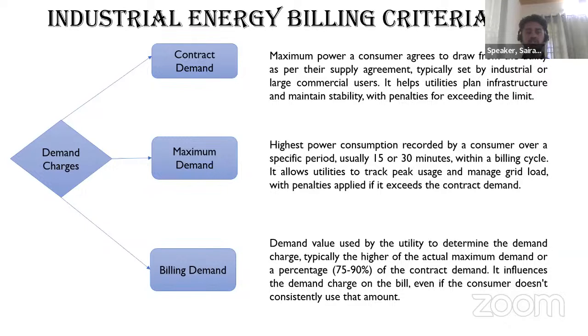Then coming to the demand charge, there are three main terms in the demand charges: contract demand, maximum demand, and billing demand. Contract demand is the demand that the user gives in an application to the grid, stating that we will be consuming this amount of demand from the grid. As an agreement, they will be planning it. There will be a mutual agreement between the grid and the user, that they will be consuming this much amount of kVA every month from the grid.